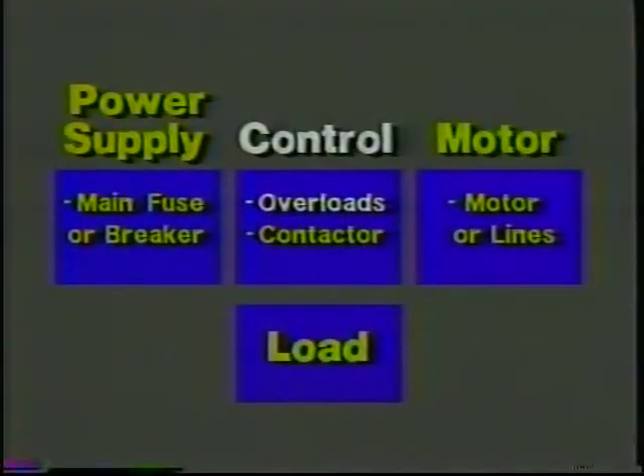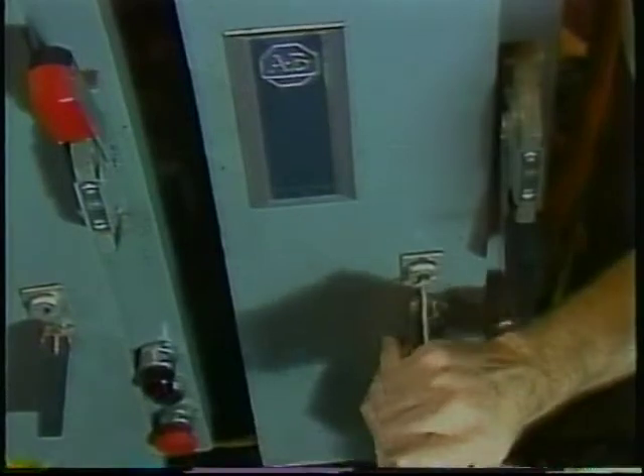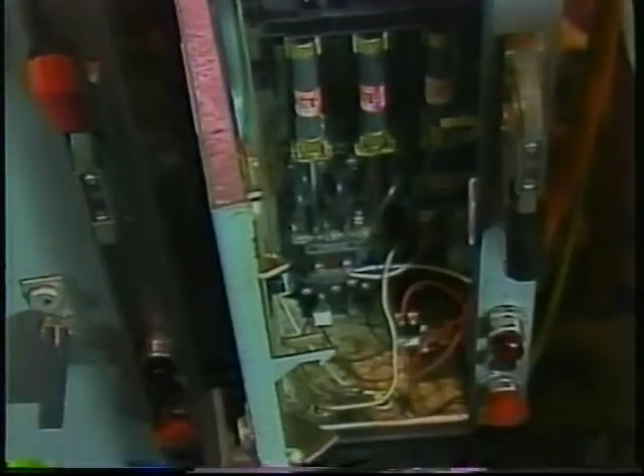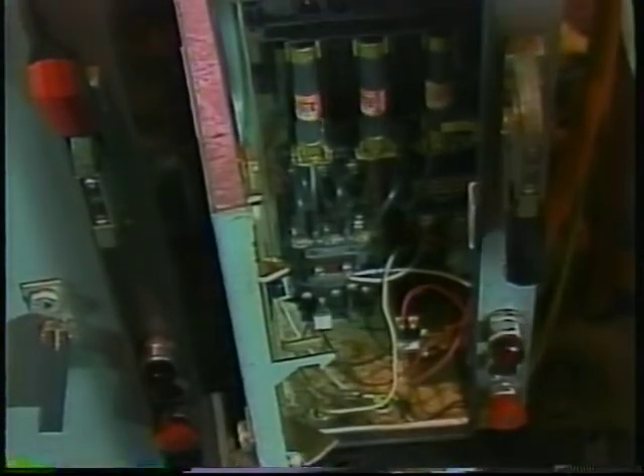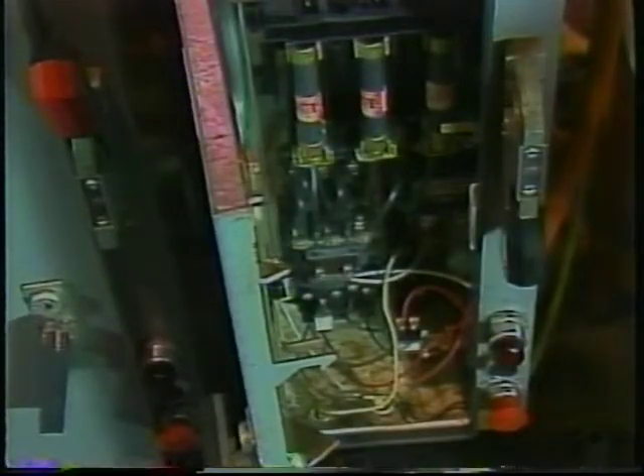Now, most overloads are set to trip when the current draw is 10 or 15% above nameplate current. If you find that the OL is tripping when the current draw is below that level, you have eliminated the motor, the load, and all the rest of the system except the overload breaker itself. Overload breakers trip when motor current heats them too much. If motor current is not too high, something else must be heating the OL and causing it to trip.